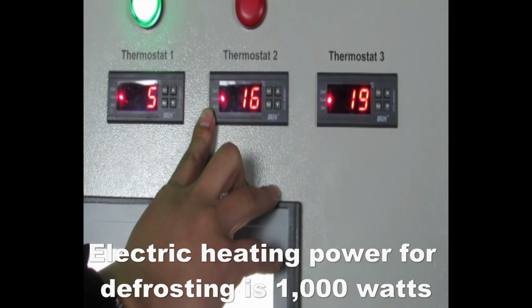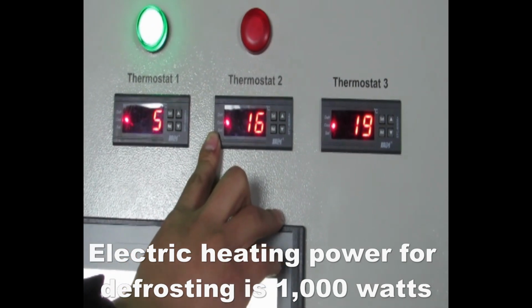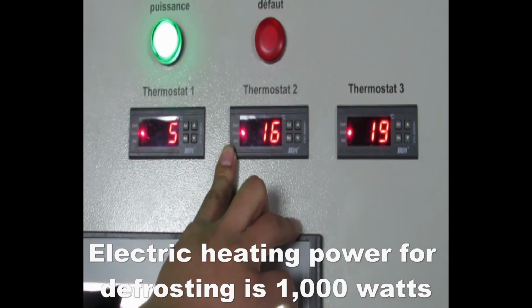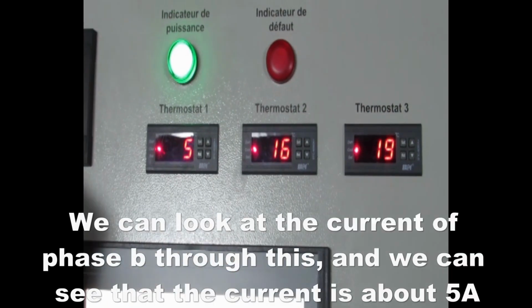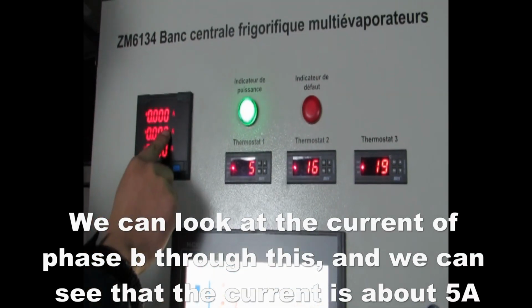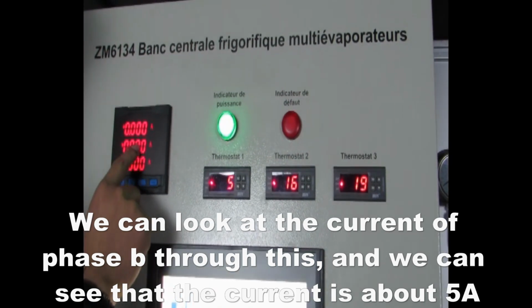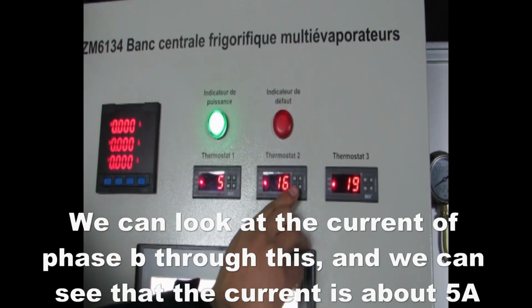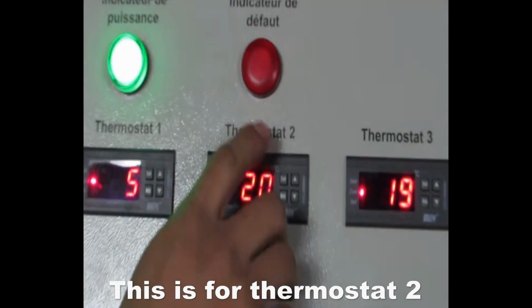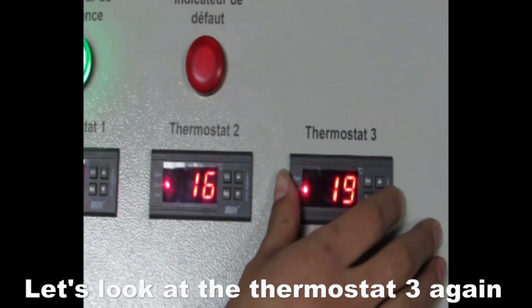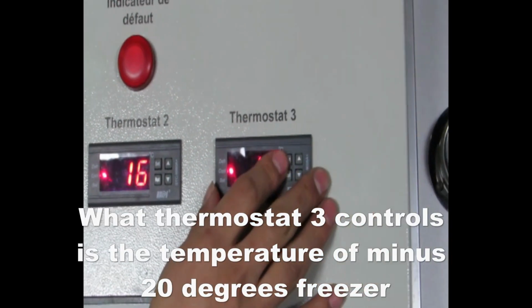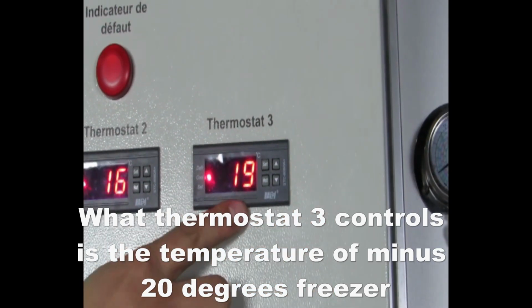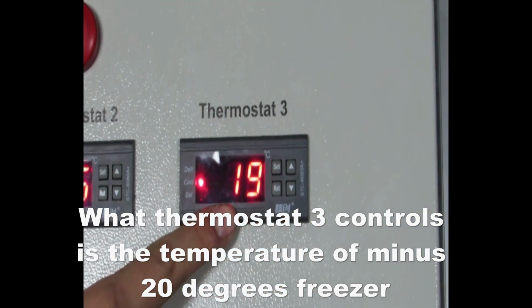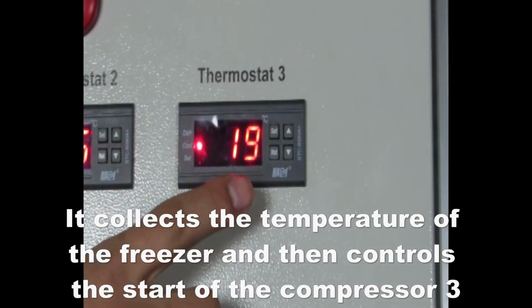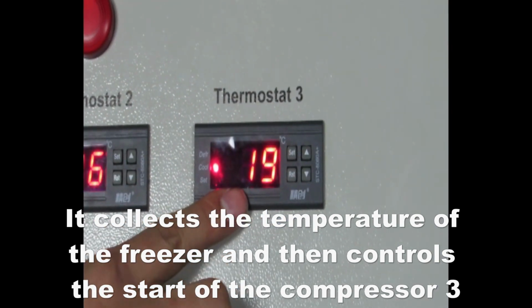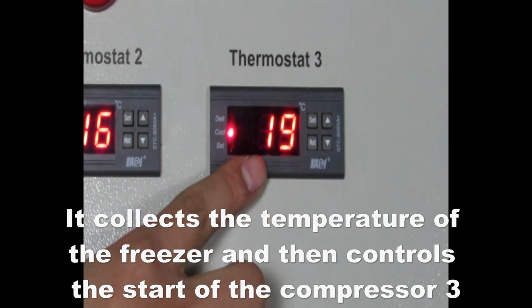The electric heating power for defrosting is 1000 watts. We can look at the current of phase B through this, and we can see that the current is about 5A. This is for thermostat 2. Let's look at thermostat 3 again. Thermostat 3 controls the temperature of the minus 20 degrees freezer. It collects the temperature of the freezer and then controls the start of compressor 3.